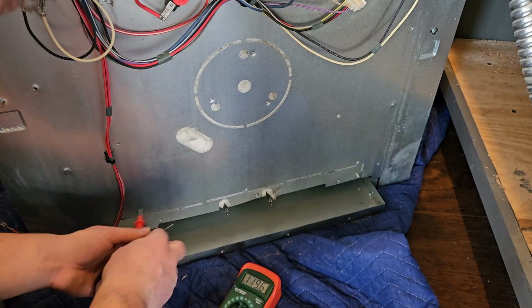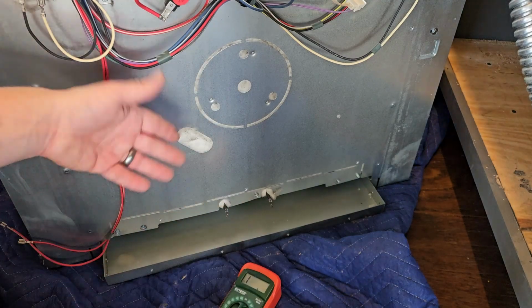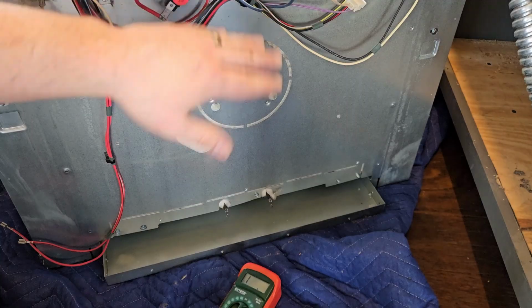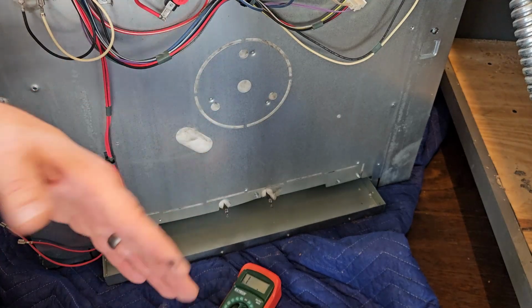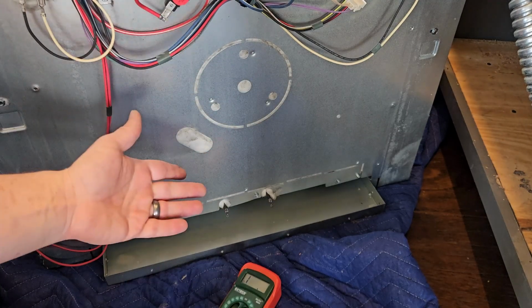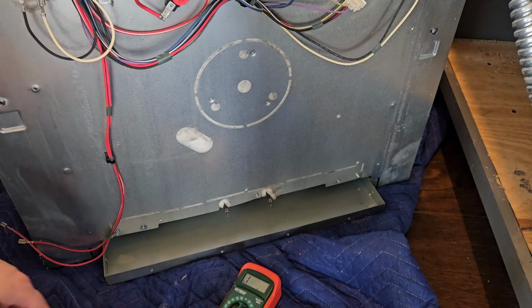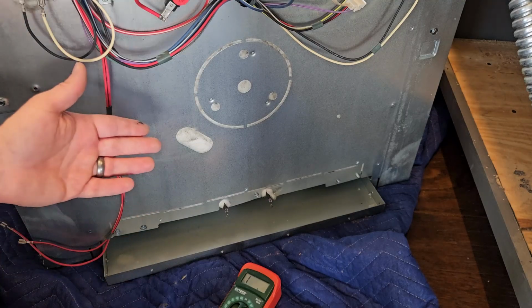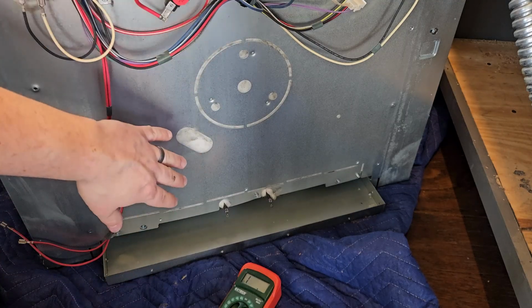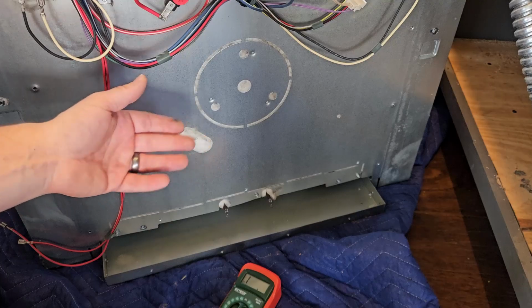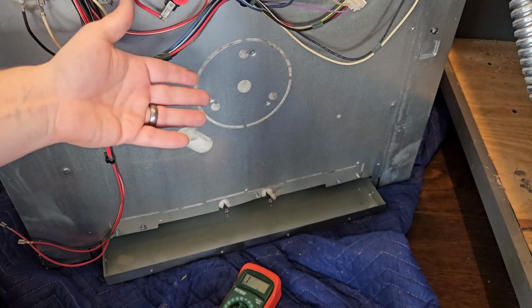19.6, that is a good reading for a bottom heating element. So we've checked our temperature sensor, we checked both our heating elements. It's neither of those. We had an error code that said it's probably the control anyway. So I've got the expensive repair. Otherwise, if one of these is bad or an open circuit, you've got a relatively inexpensive repair here.